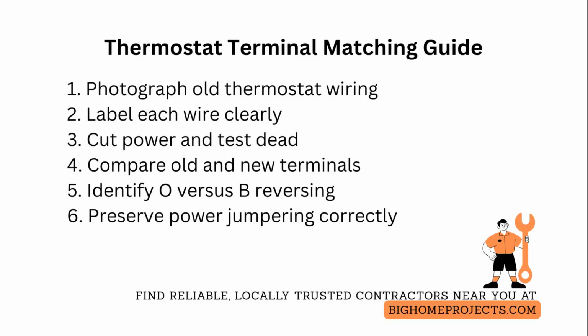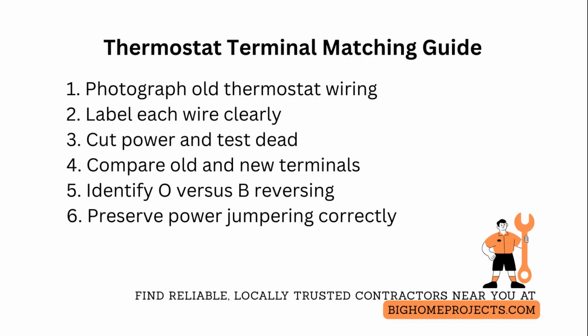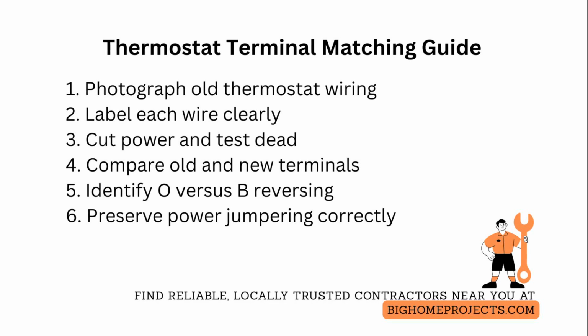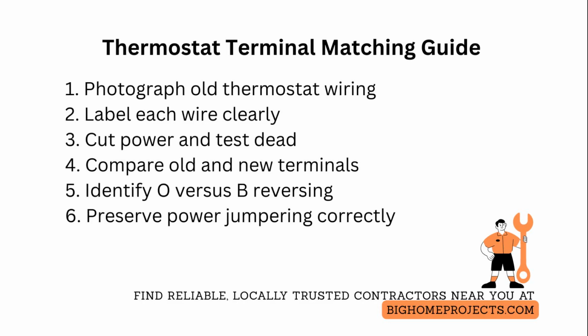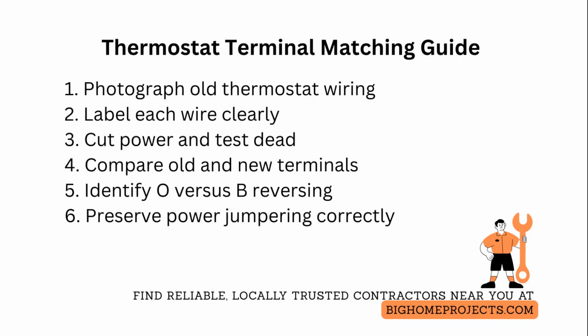If your control board has multiple R terminals or jumper blocks, ensure the new stat's power source links are preserved. Some thermostats require a separate 5-volt or 24-volt common, and improper jumpering can leave the thermostat unpowered or backfeed the transformer. For 2 transformer systems, or heat and hydronic mix systems, isolate each transformer and confirm diodes or isolating relays exist. Never tie 2 R terminals together without a diode or relay intended for that purpose.